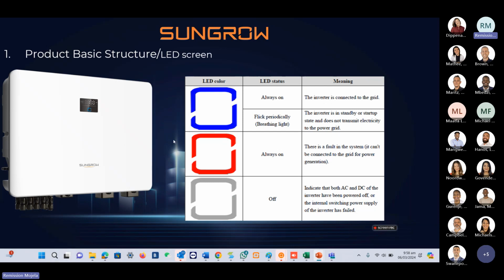Basically all our products have the same sort of LED indicators. If the LED indicator is solid green or solid blue, it means that the inverter is connected to the grid. If it's flickering, it means the inverter is on standby. The only way for the inverter to be on standby is that either the grid or the DC power is completely shut down. When the indicator is completely red, it means there's a fault that is preventing the system from actually starting up. And when the icon is completely grayed out, it just means that the inverter is completely shut down. It doesn't have any AC or DC power coming into the inverter.